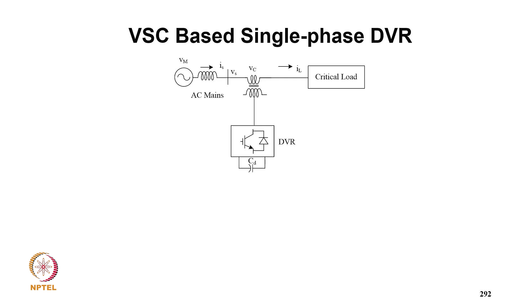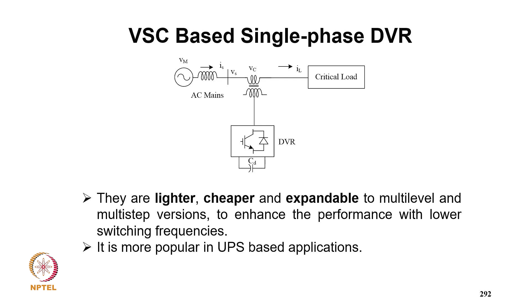So this is typically a single phase DVR, dynamic voltage restorer, where the voltage source converter is used to inject the right voltage in series with the line. So they are lighter, cheaper, and expandable to multi-level and multi-step versions to enhance the performance with lower switching frequency, and it is more popular in UPS-based applications.